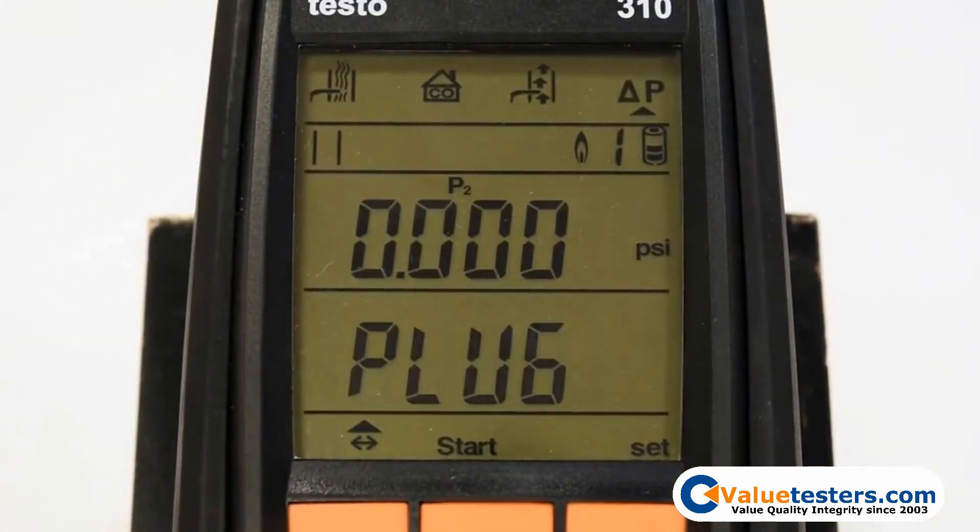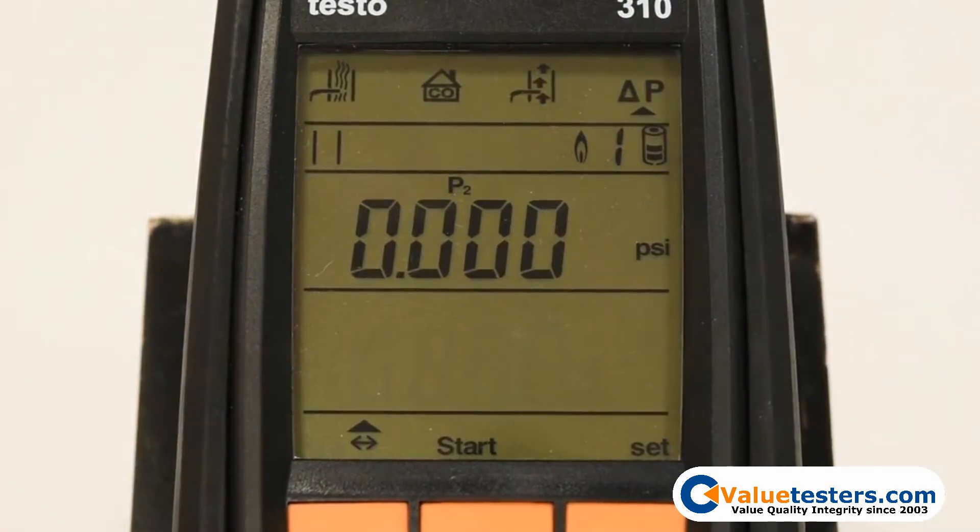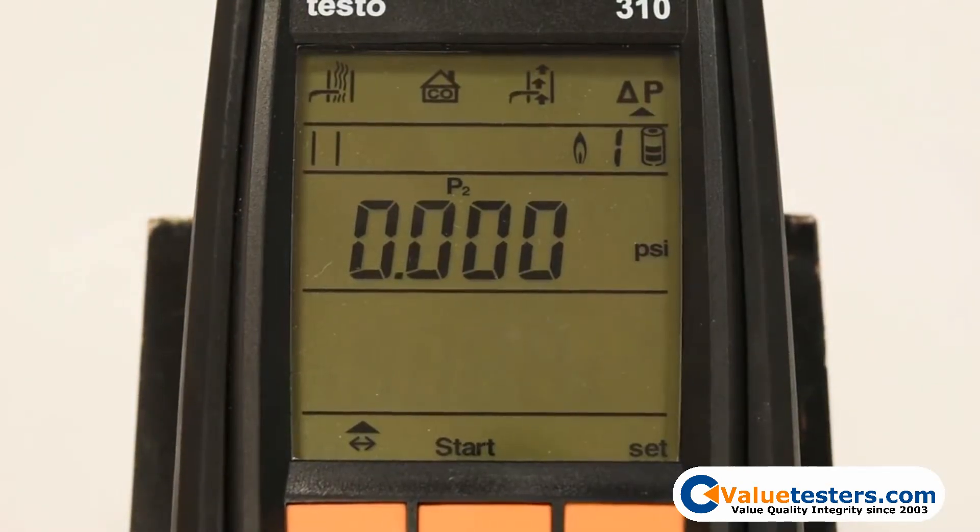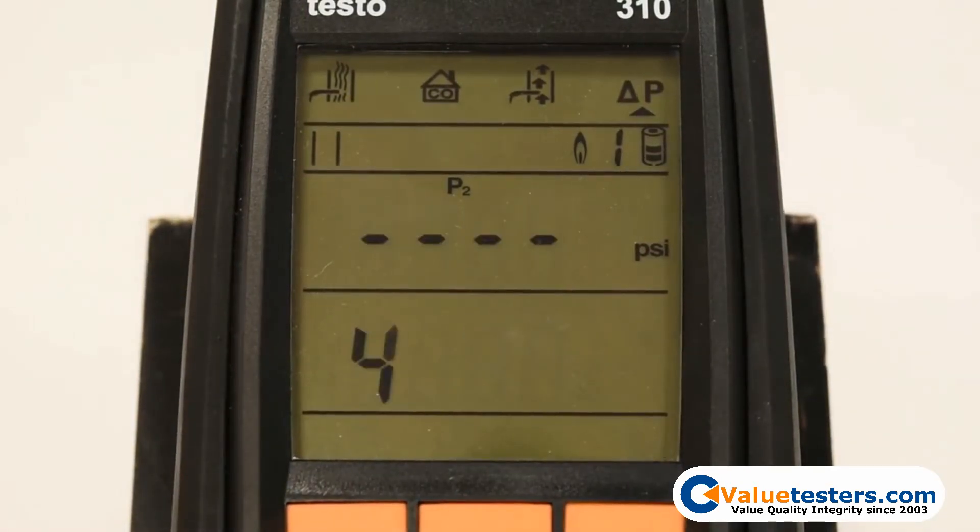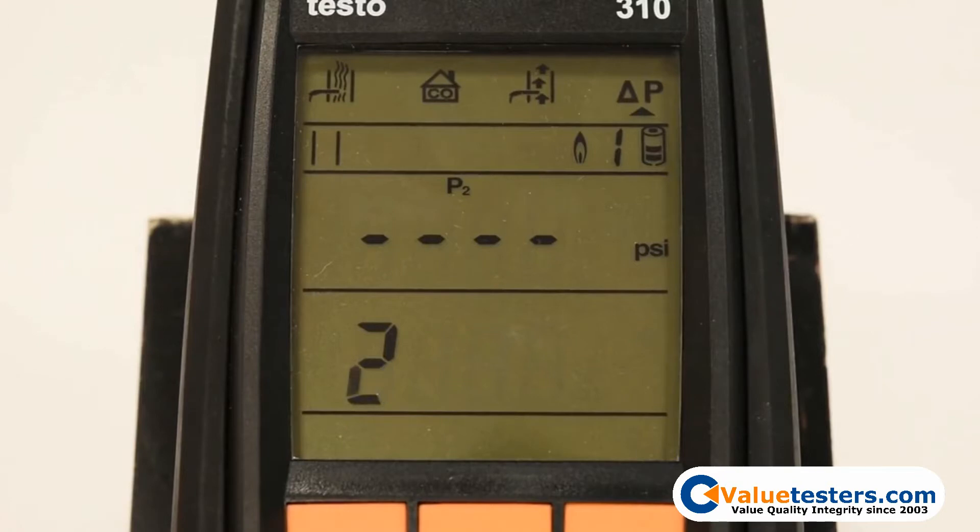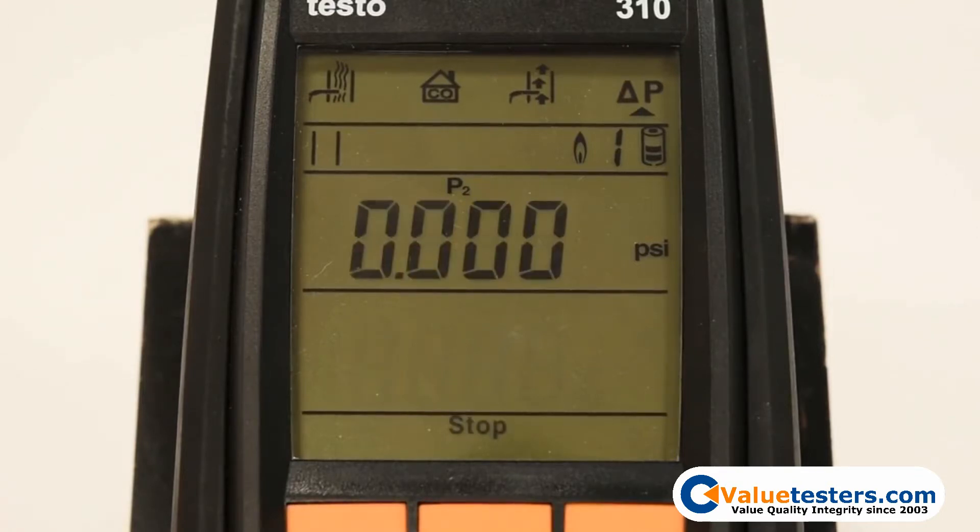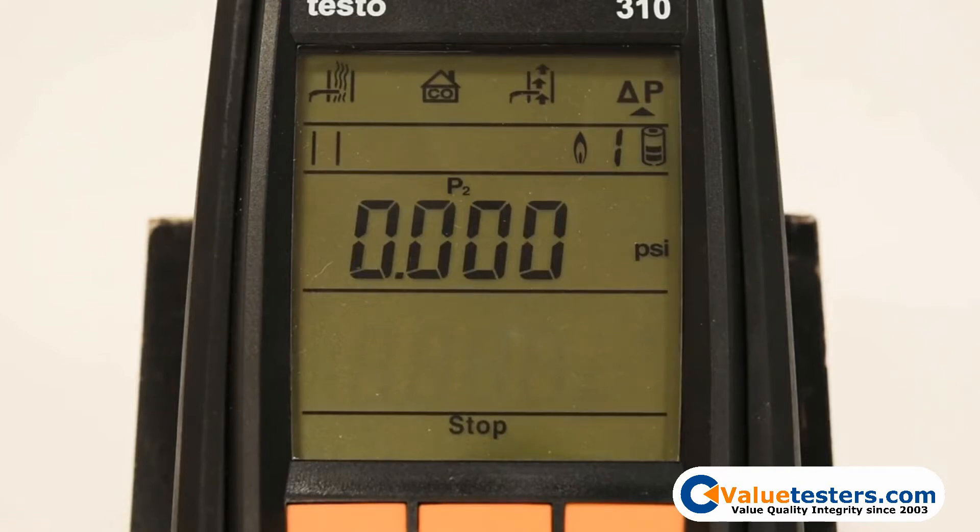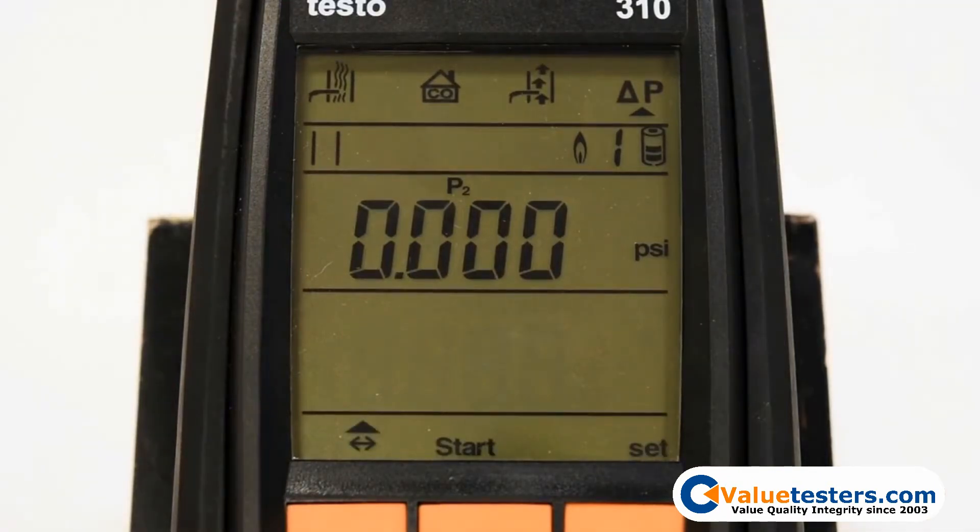You will then start your measurement with the start-stop selection indicated above the center orange button. The display will begin a countdown to zero the pressure reading. Once the zeroing is completed, you may connect the other end of the silicone hose to your measuring point. After the measurement is complete, press the center orange button again to stop your measurement.